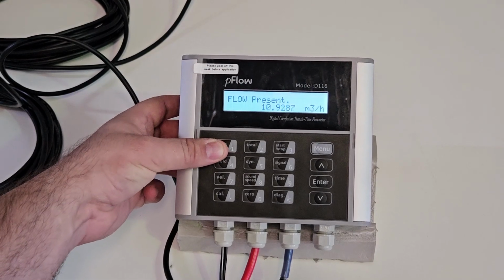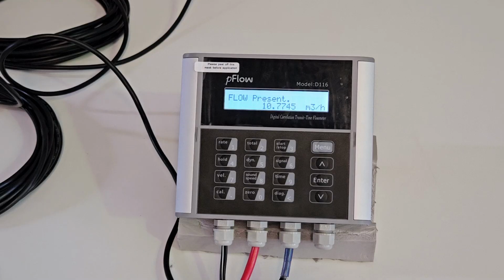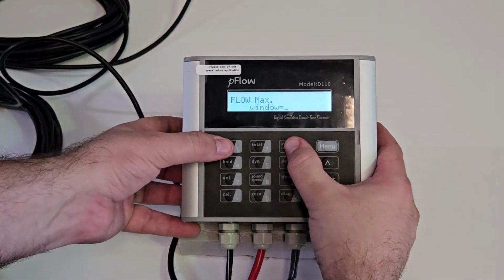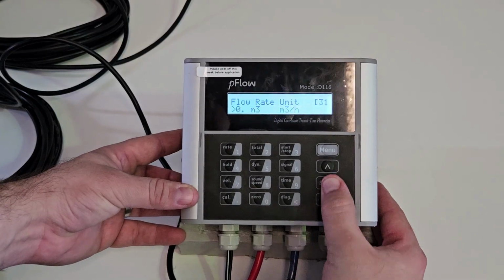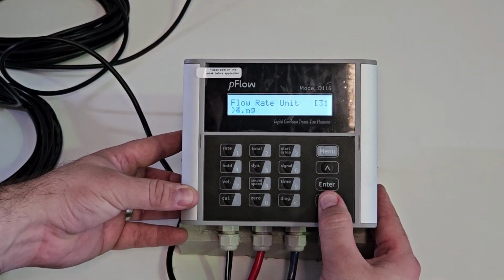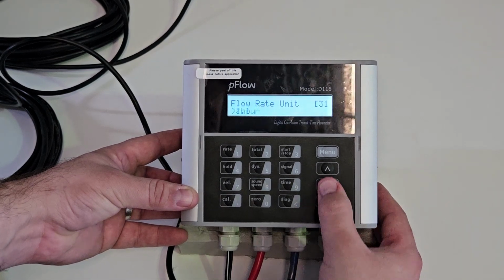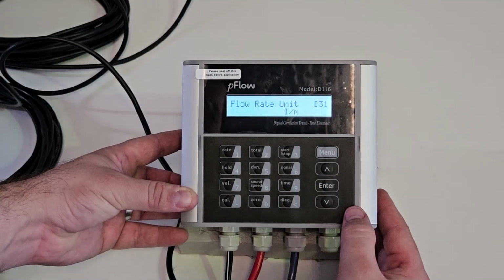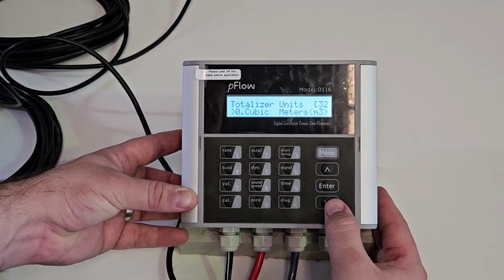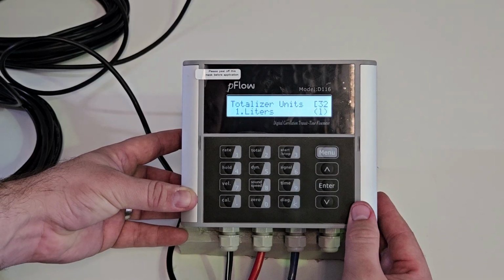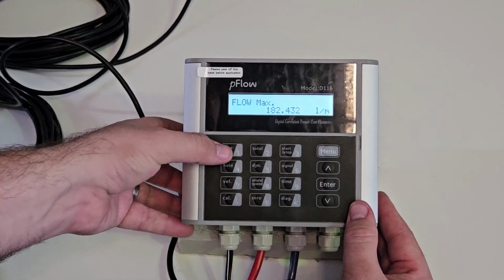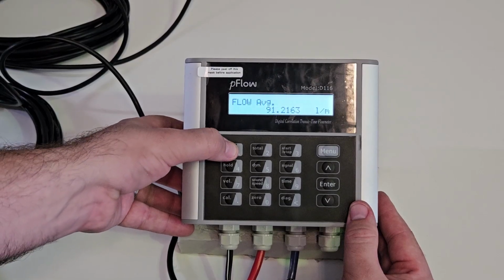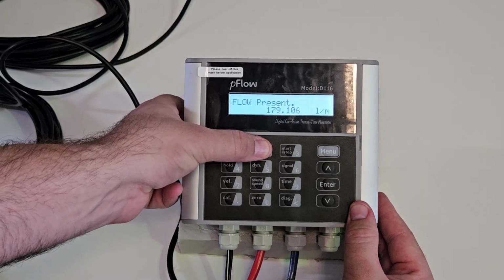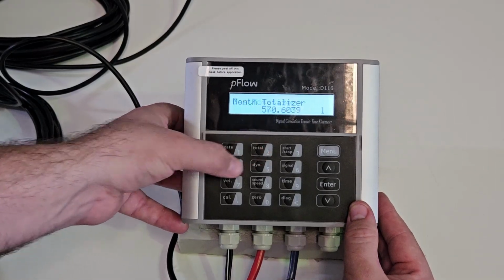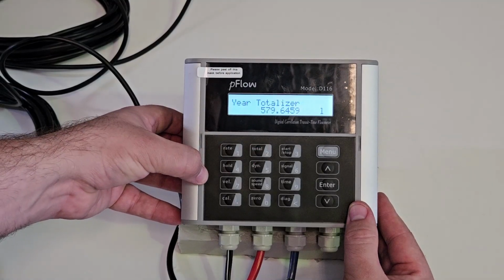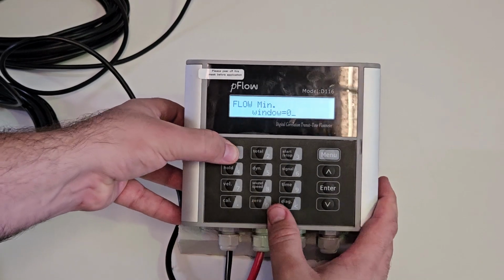Now you can press the rate shortcut to toggle between the various flow displays. If you want to change the flow units, go to menu 31. Press enter, scroll the list of units, then enter to select. You can then choose a time unit. In this example, I set it to liters per minute. And you can also change the totalizer unit. Again, for example, I have set it to liters. Now on the rate display, my units have changed as it was set. Also on the totalizer display, the unit has changed as it was set. You can also enter menu 01 to show the flow rate and velocity.